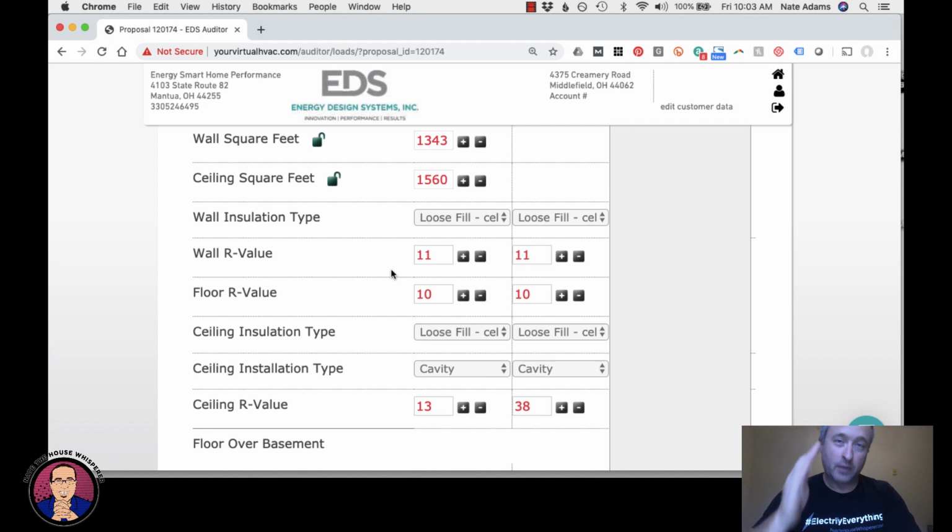So you run where the house is now, where it could be with a 30 to 50% reduction in leakage, and then you want to try and figure out how leaky the house would have to be to actually have their current equipment be right sized. So you get an idea of the range where the load calculation could be.